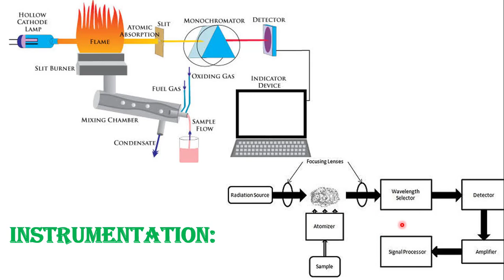Then electromagnetic radiation is passed over the atoms of ground state, which absorb their own characteristic wavelength and are excited to a higher energy state. Then the radiation will pass through the slit followed by the monochromator. This monochromator allows the particular wavelength of its element to be analyzed. The detector detects the radiation and generates an electrical signal, which is proportional to the intensity of light. Then the indicator device reads out all data on absorbance and records it. This is the block diagram for atomic absorption spectroscopy.